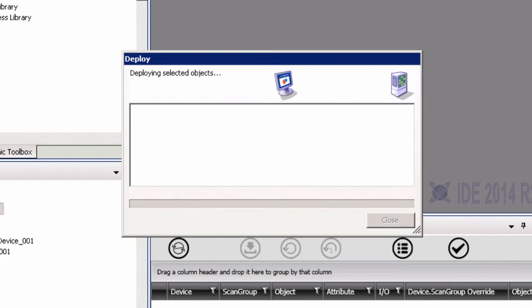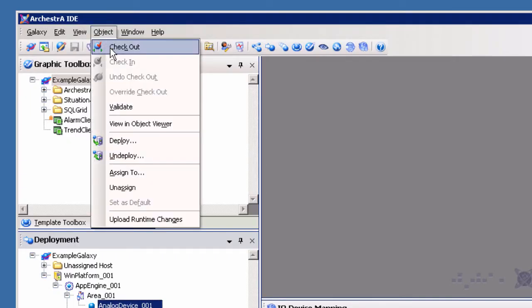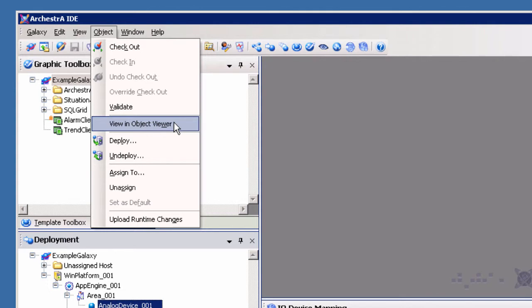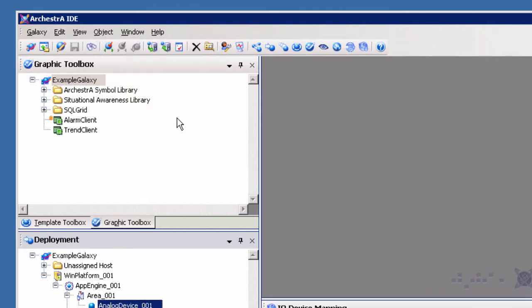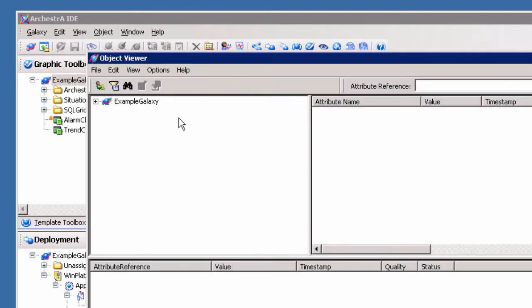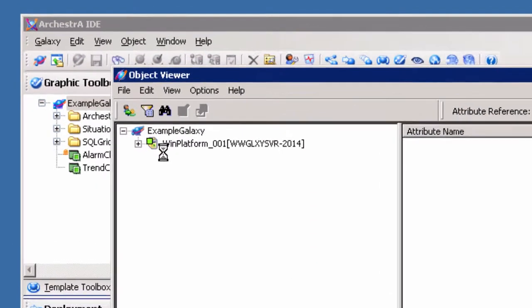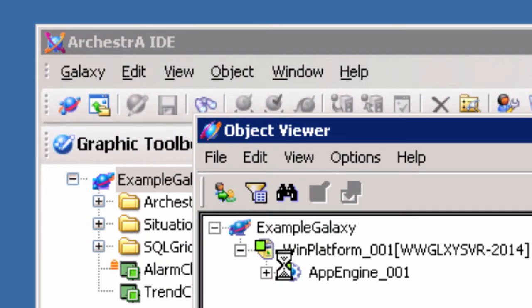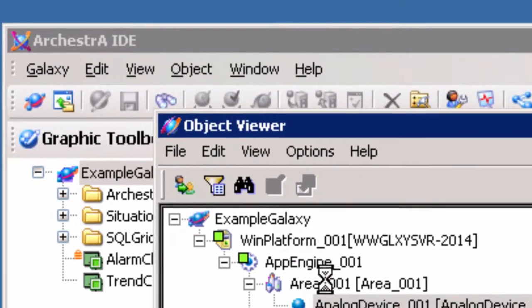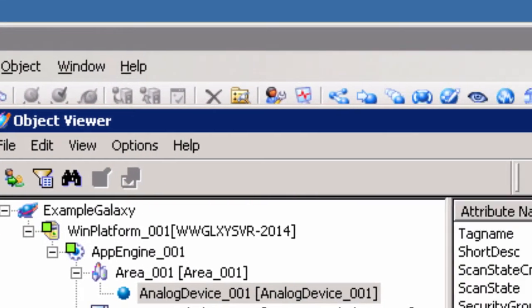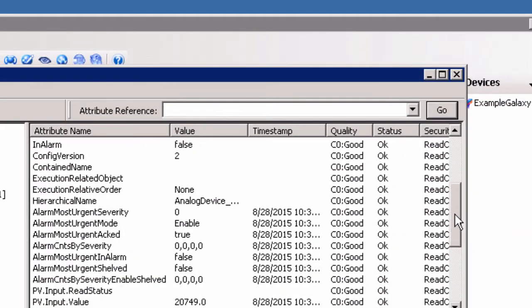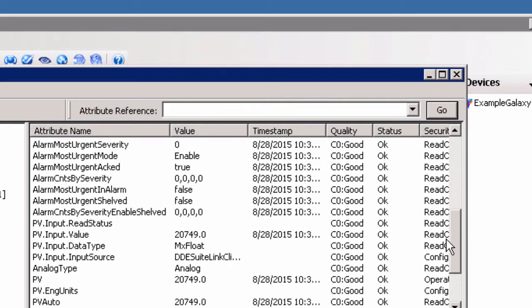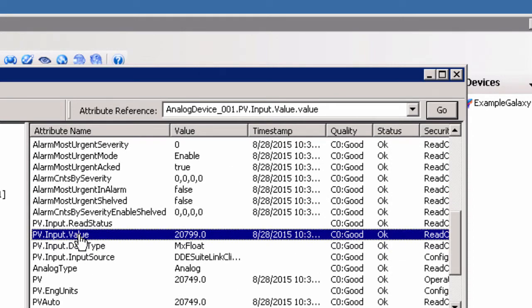Once the deployment process is complete, click Close. You can now view the live data by opening the System Platform object viewer. Highlight the Analog Device object in the deployment view and navigate to the Object menu of the Archestra IDE interface. Select View in Object Viewer to open the Object Viewer and see the present value and quality of the item. To subscribe to changing values, right-click on the attribute and select Add to Watch. This adds the attribute to the Watch window located at the bottom of the interface.